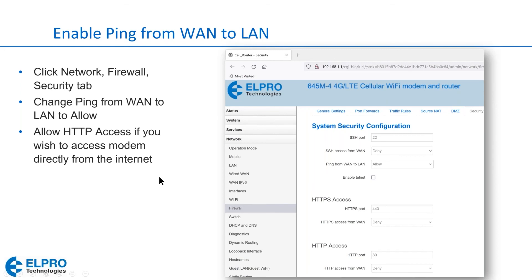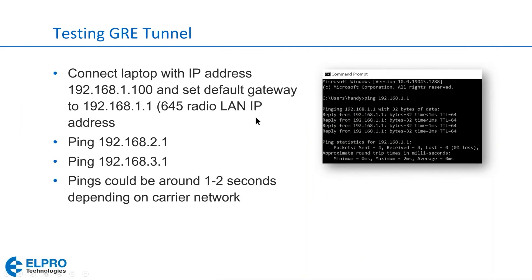Once connections are set up, connect the laptop with IP address 192.168.1.100, set the default gateway to the LAN IP address of the 645 connected to it, then do a ping command — ping the remote modem and also ping the remote PLC connected to it. This example shows a typical ping command. Your pings could be around one to two seconds depending on the carrier network. Some carriers are a little faster, some areas have stronger signal. In areas with poor coverage, pings could be quite a bit longer.